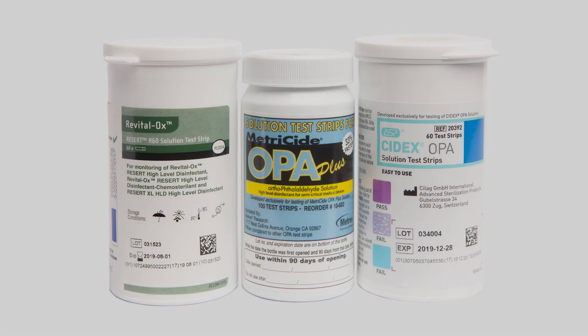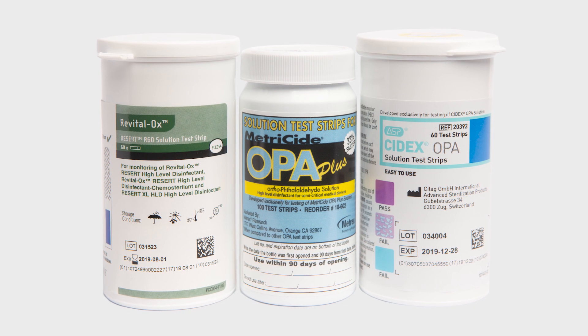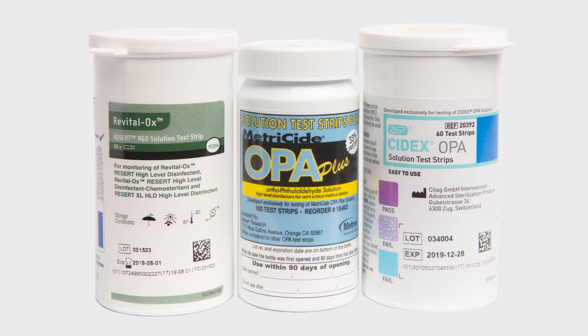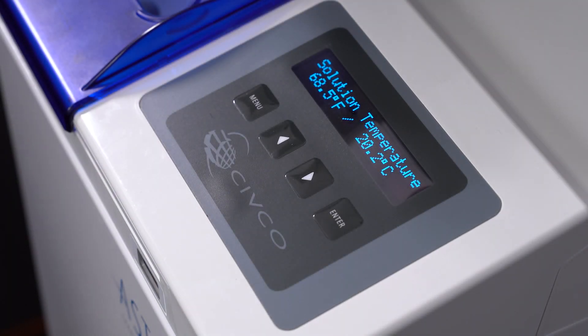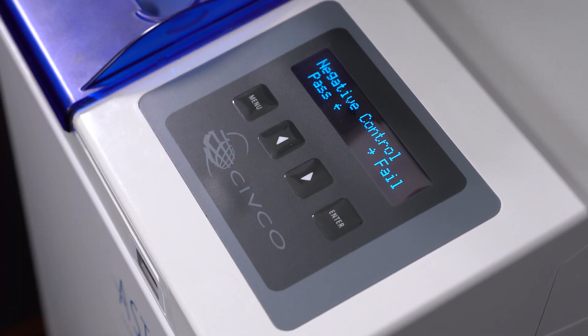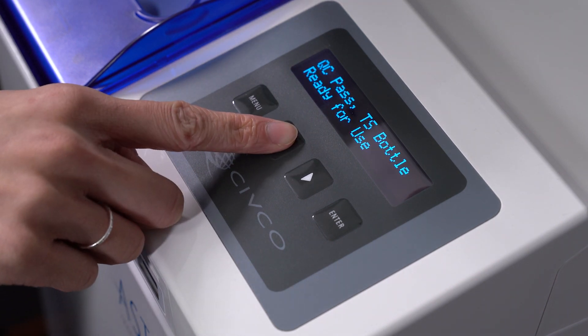The quality control test for a new bottle should now be performed according to the disinfection manufacturer's instruction for use. Once the test has been completed, enter the results in the Astra for traceability and storage on the log. First, provide the solution temperature and adjust if necessary. Then, enter the positive and negative controls. The display will read: QC Pass TS Bottle Ready for Use.